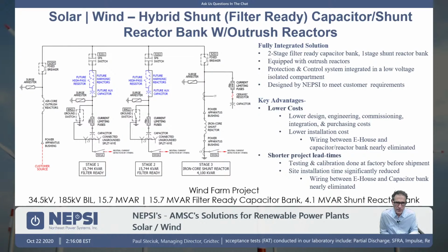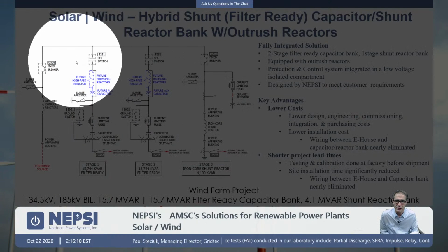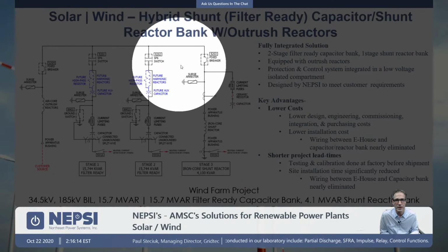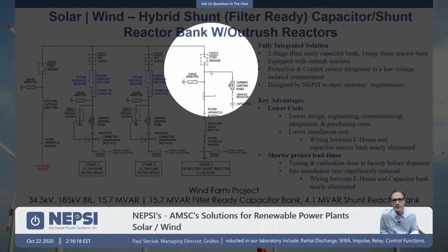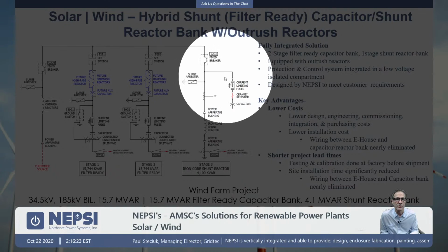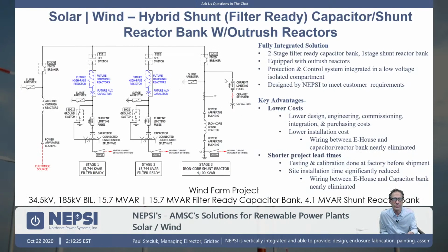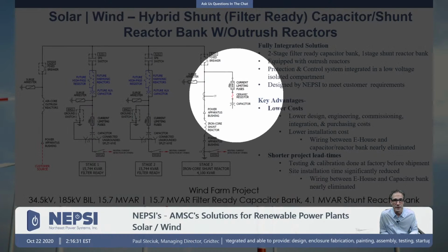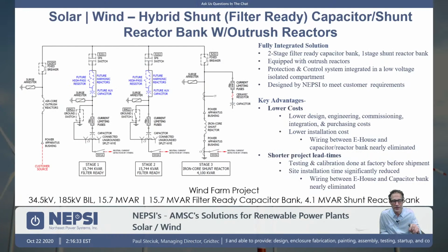So, an interesting thing to note here is that the switching device oftentimes plays into the cost of the equipment and also the delivery time of the equipment. So we're going to talk about that too in a moment. Over here we have a shunt reactor bank, and you can see here we put in an RC snubber. So shunt reactor switching is a very difficult process. We like to use an SF6 breaker, and we put in an RC snubber here to reduce any possibility of reignition within the breaker itself.